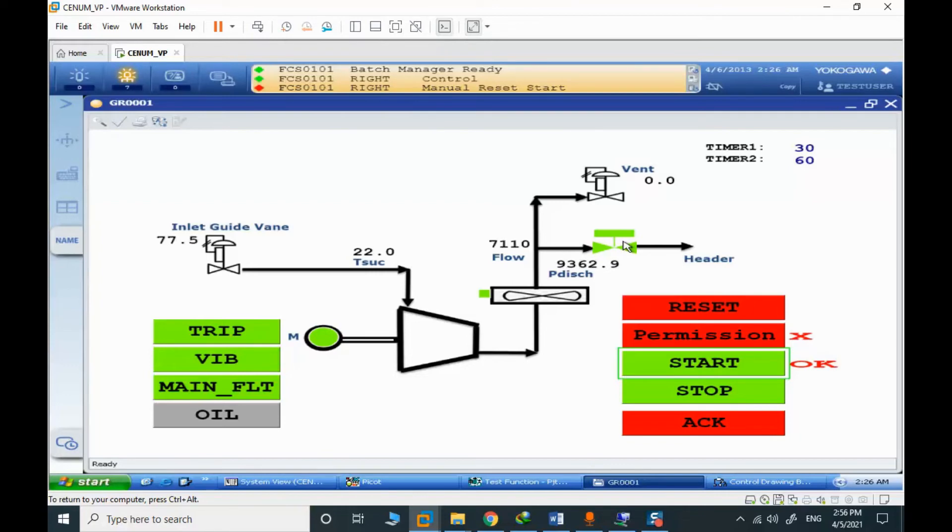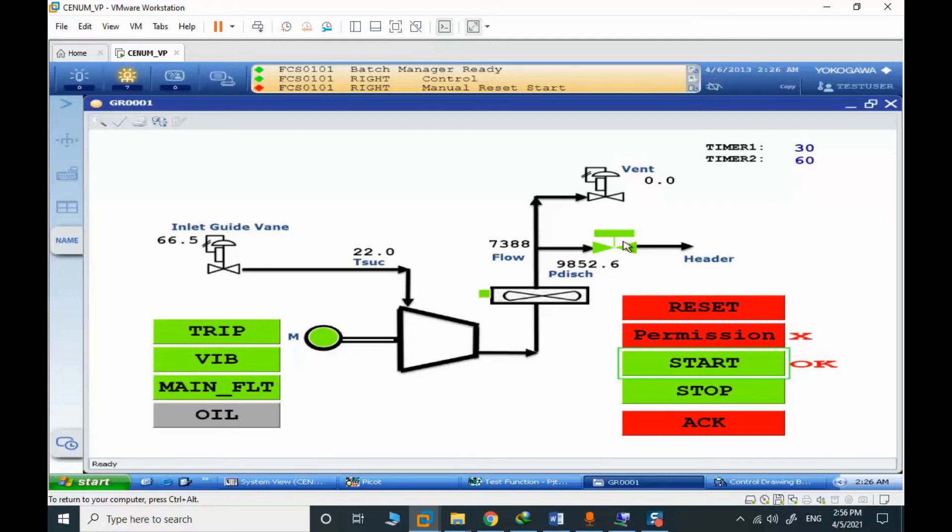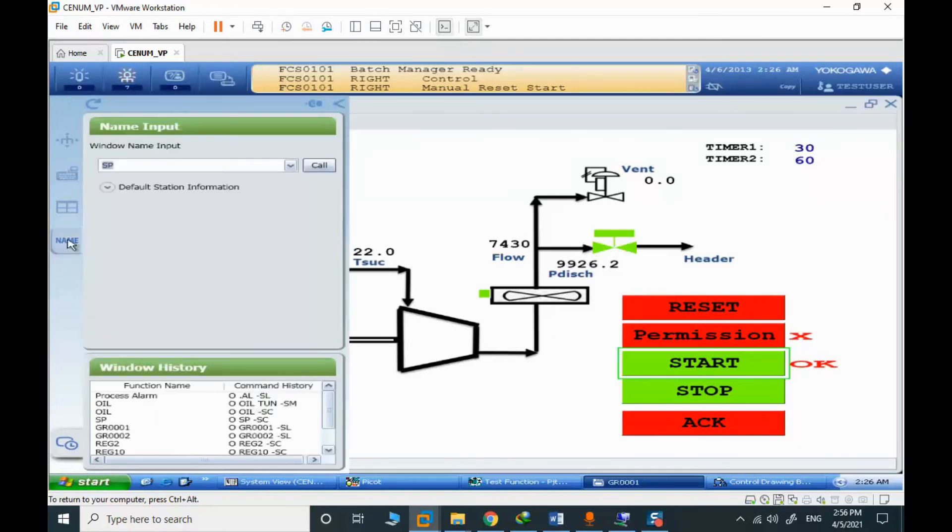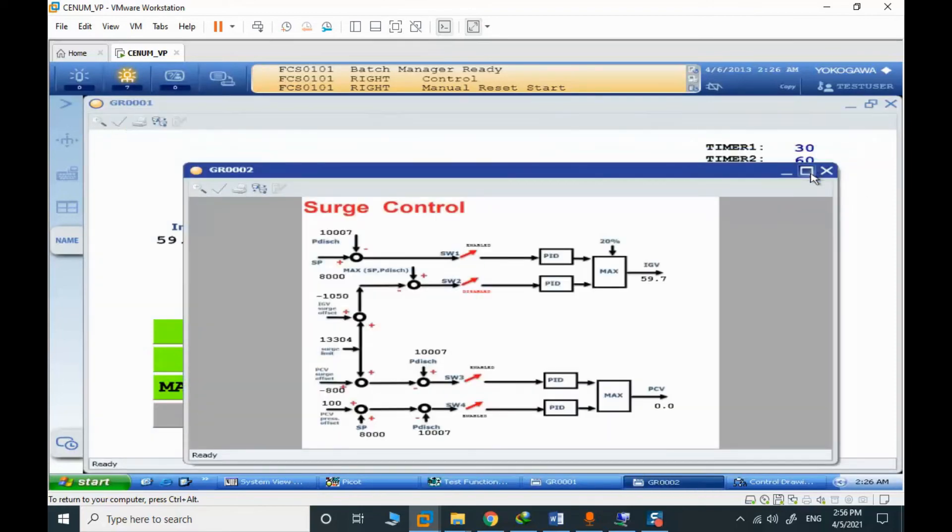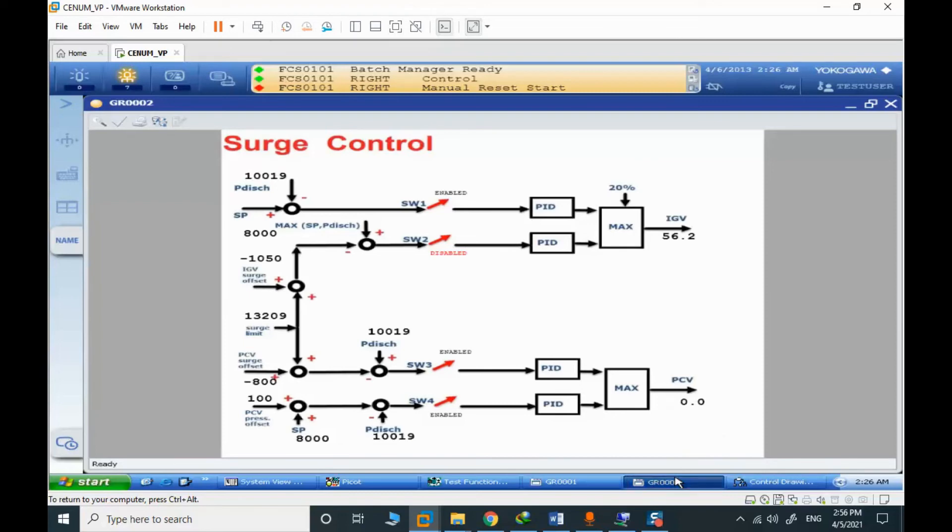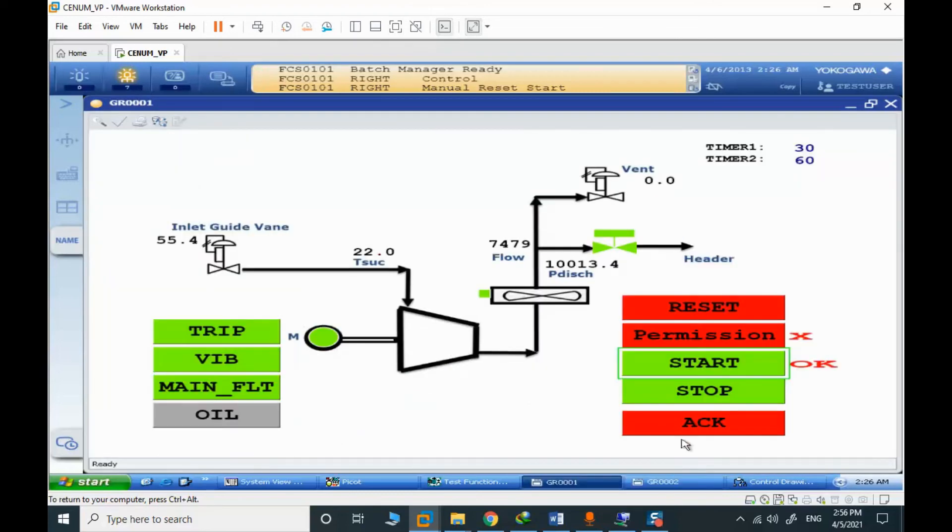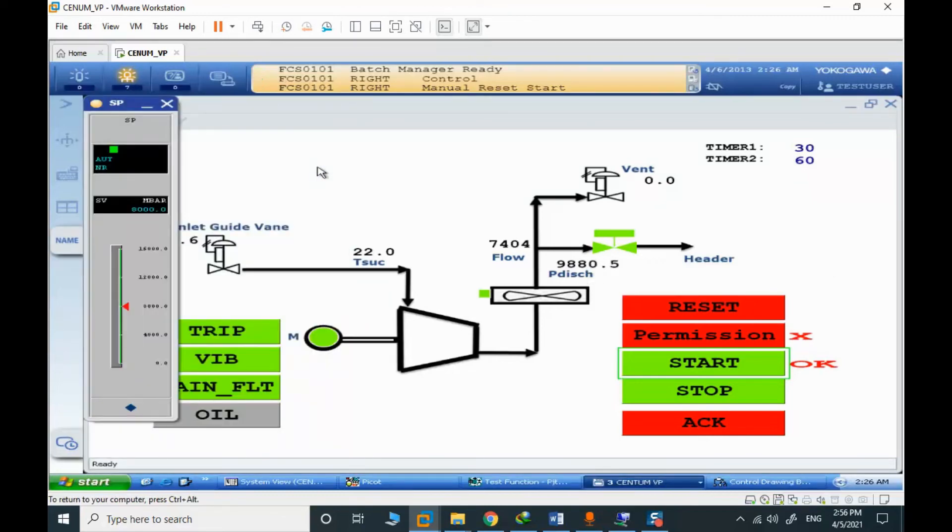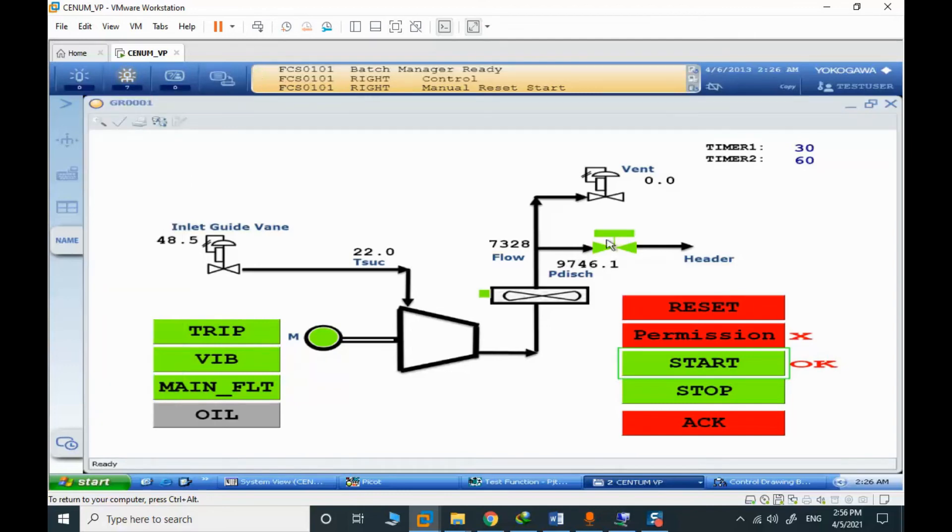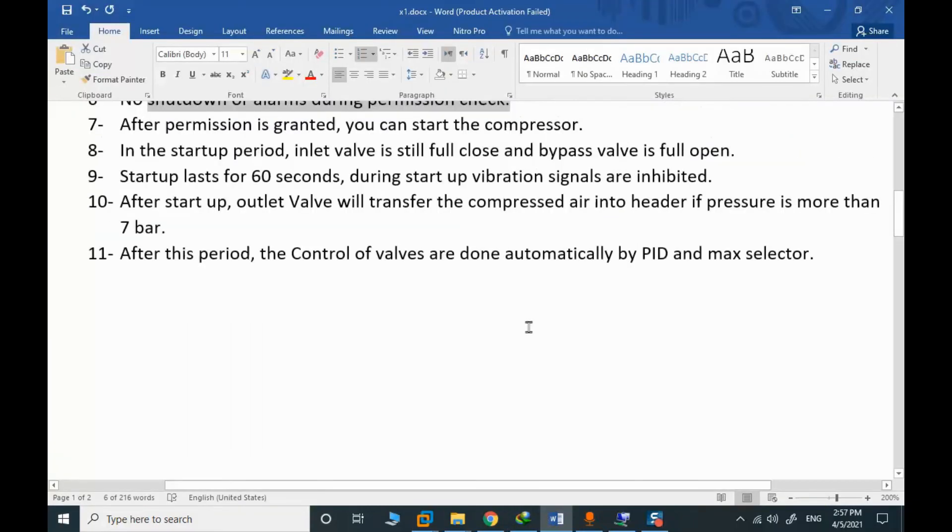This is the normal operation. The PID controller is in action. And you can see that we have included the PID controllers here. This is the override structure. And this is the normal operation. You can see we should reach to the set point of 8k or 8 bar, 8,000 millibar or 8 bar. And after a while, we will reach to that. And the startup lasts 60 seconds.